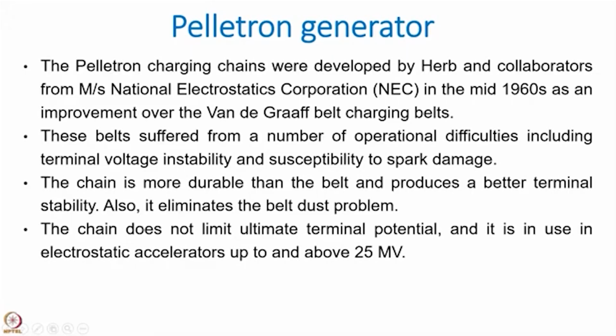The belt suffered from a number of operational difficulties, including terminal voltage instability and susceptibility to spark. As I said, because of that high voltage, corona needles or mesh, sharp surfaces were formed on the belt, and therefore those belts were subjected to sparkings. And those things are avoided in the case of Pelletron, because pellets which carry the charge are conductors, and therefore charge will be uniform and there will not be any spark. There is no voltage gradient or electric field over there.